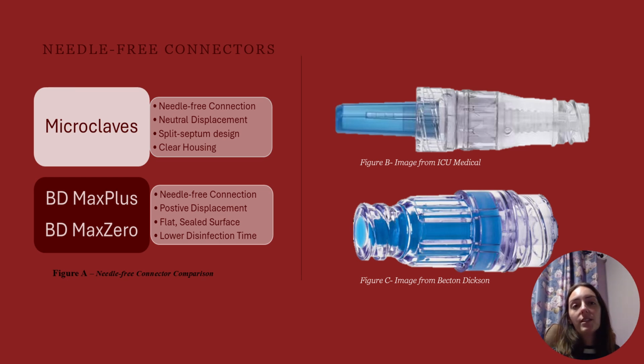Septum versus flat sealed surface. The split septum inside the Microclave is designed to re-seal after disconnecting from the catheter. However, this design has gaps and holes on and around the tip that allows for the presence of bacteria and the potential for colonization. BD Max needle-free connectors have a flat sealed surface to guarantee bacteria does not colonize on the tip of the connectors. This design permits a lower disinfection time of 3 seconds compared to Microclave's 15 seconds, allowing for nurses to work more efficiently and provide a safer care to our patients.